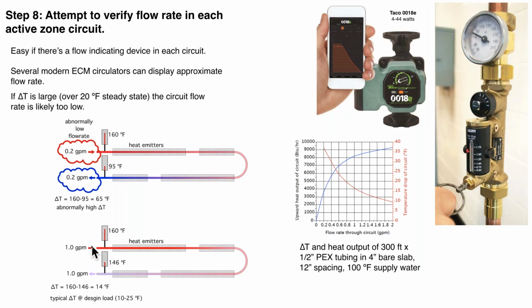Okay, here we've got a flow rate, we've gone up to 1 gallon per minute. We're going in at 160, we're coming out at 146. We've got a delta T of 14, much more reasonable. Okay, and just to show you, I made a plot here. I've had this plot for a while. This is a floor heating circuit.